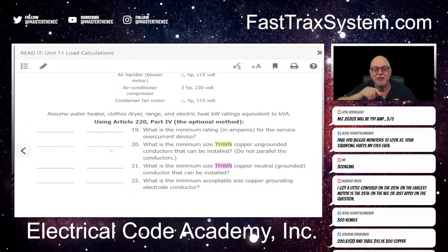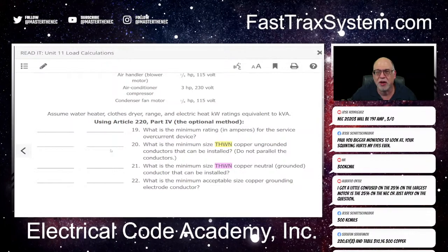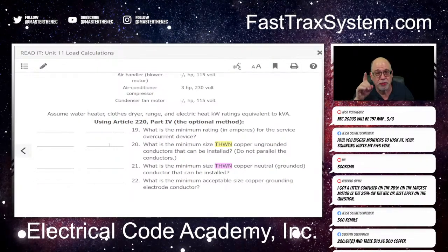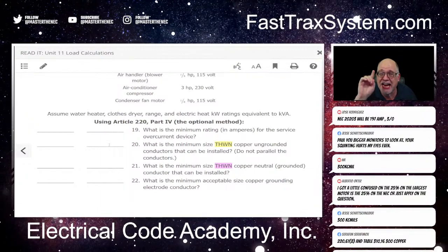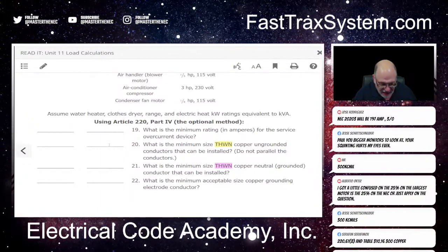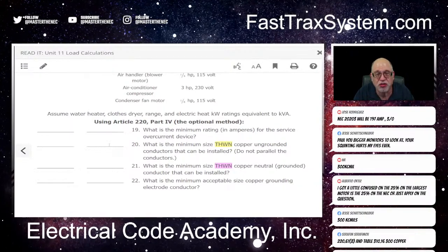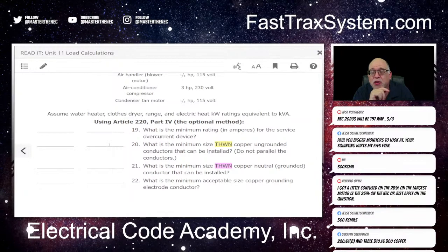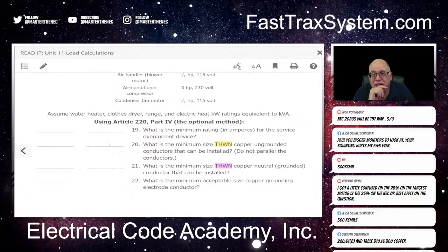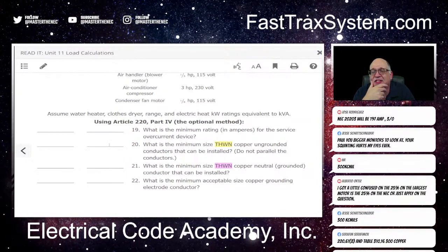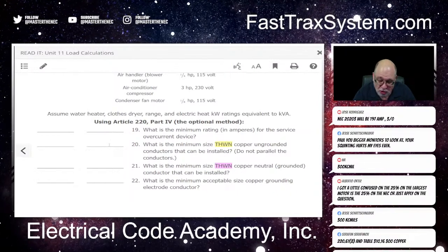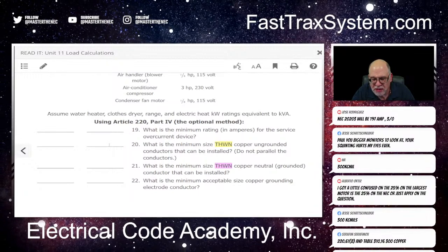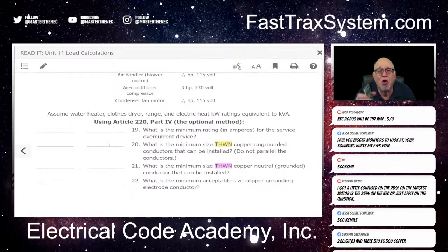Oh, look, Jose's already done it here. So in our case, what are we going to do under the 2023? Because under the 2023, there's an and in there. So now I get to take that same value, that 282, and what do I get to do? The first 200 at 100%, and the value over that at 70%. So that's 82, right? So 82 times 0.70 is 57.4.